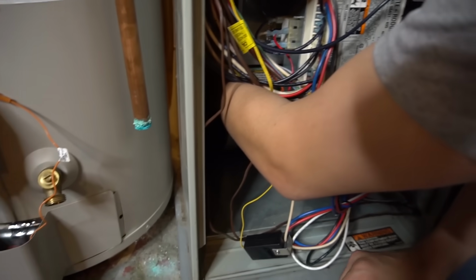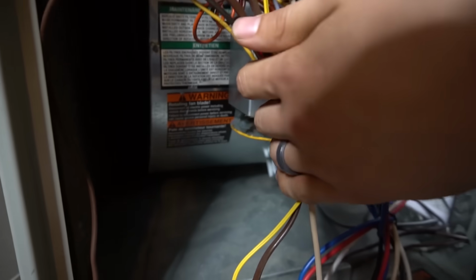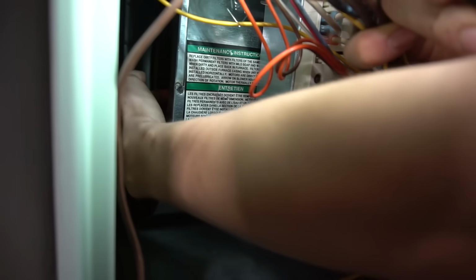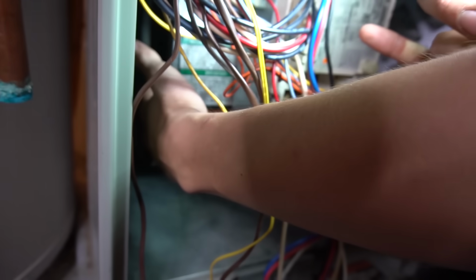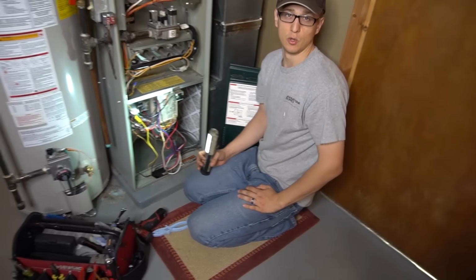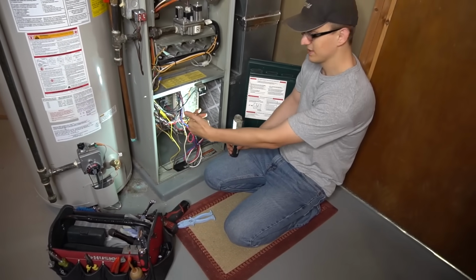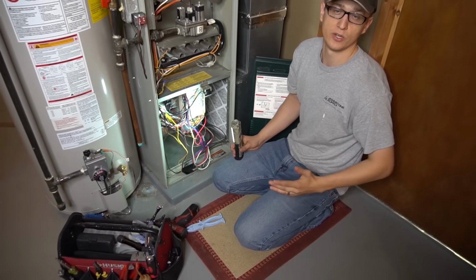You're not going to be able to see that on camera, but if you take your bottom door off and reach in, you'll be able to see that, feel that wheel. Give it a spin. If it's very crunchy, feels like it's seized up, in that case you will need to replace your blower motor. I have a video of how to replace the blower motor. If you want, you can check that out. I'll put that in the description below as well. If your motor is seized up, you do have to replace that motor before we go any further.